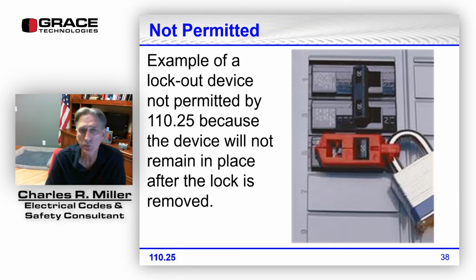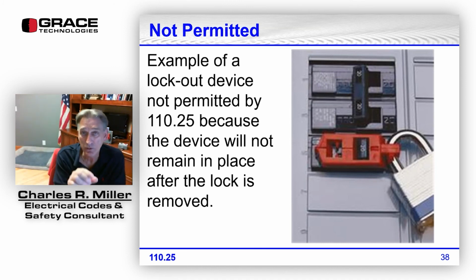is just a 120 volt motor, and so it's out there, it needs a disconnecting means within sight. There is no disconnecting means within sight, so it has to have a lockout device on the breaker that would remain in place once the lock is removed. Well, it's fine. It's perfectly fine to use this, but not if it's required to have this in accordance with the National Electrical Code.